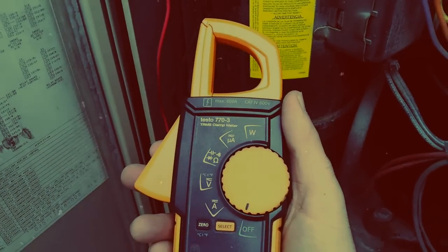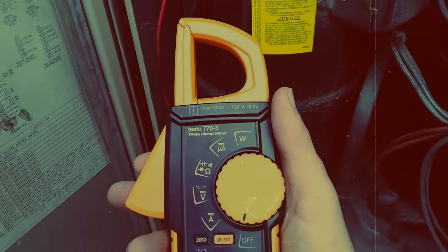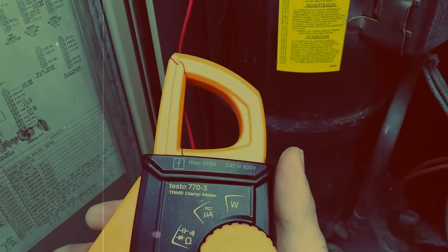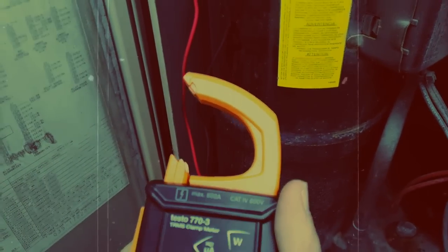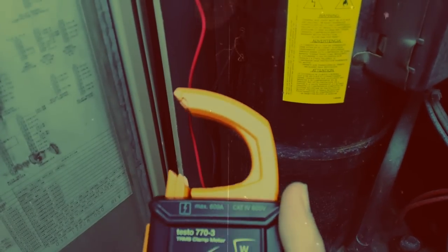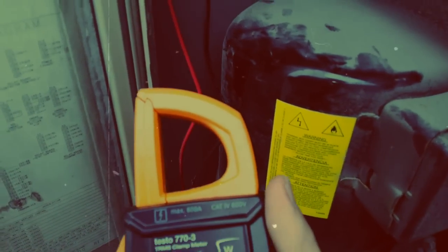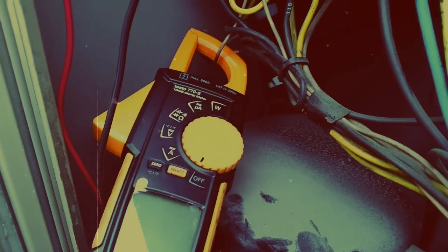So now we've got our system running, and we're going to check this capacitor under load. First I wanted to show you the clamp feature on the amp probe, and how it drops down. Now that allows you to hook on to the wire, rather than trying to grab it like conventional style amp probe. So what we want to do, we want to hook onto the start winding of the motor. This is a condenser fan motor by the way, and the motor is brand new, just so you're aware.